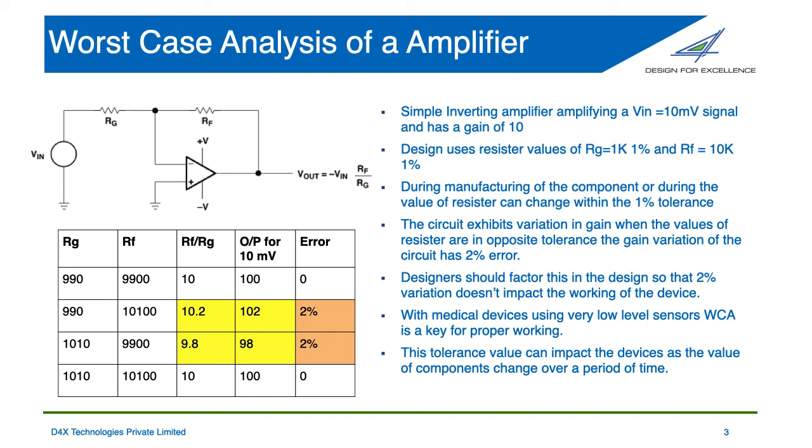So the key thing I would like to mention is to keep in mind that the tolerance of the components will ultimately have an impact on your design. The catalog value of a part is not that important as compared to the tolerance. So when you do a design with a resistor or a capacitor or an inductor, please do understand the value of tolerance, and remember, your error can go out of control if the tolerances are in the double digits. And this is very key for a medical device, because medical devices handle very low level signals.